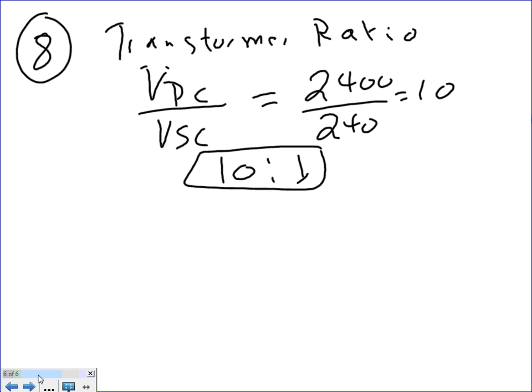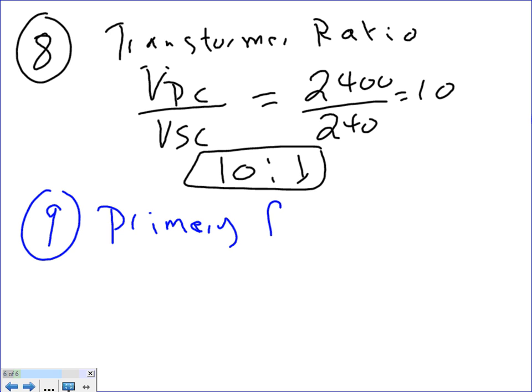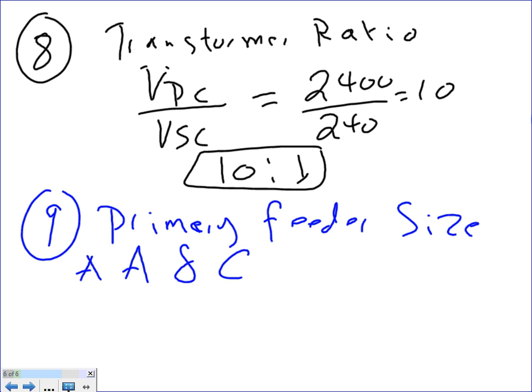Okay, number 9, I'm going to find primary feeder size. For primary feeder size, guys, I want to split it into 2, for phase A and C. For A and C, what was the amps when we sized them? You guys remember for A and C on the primary side, what was it? 94 for A and C. Together, on the primary side, they were 91...